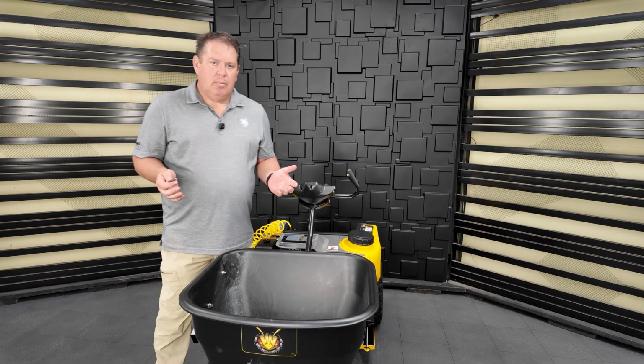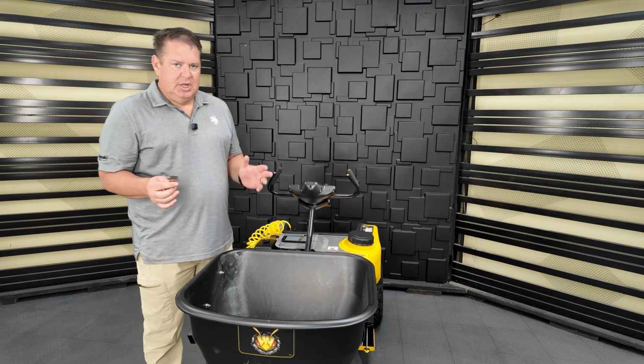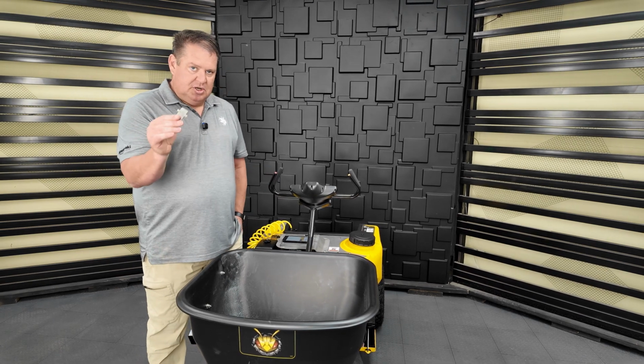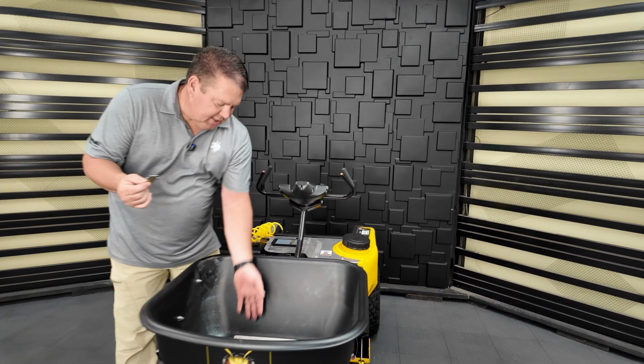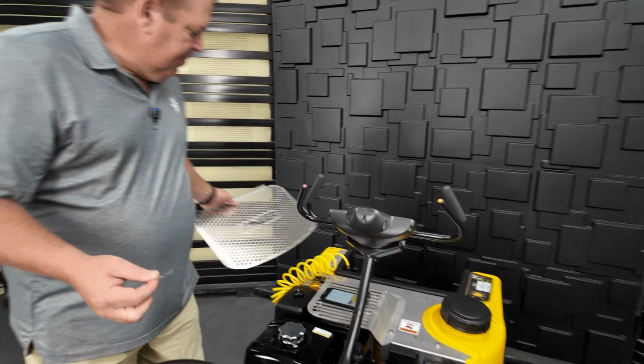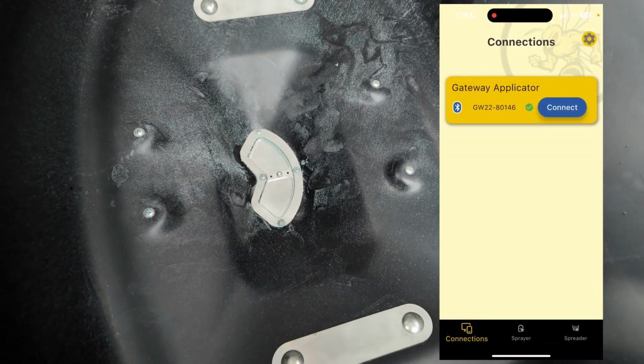The first thing you do in the calibration process, or even setting up any machine, is set the min and max position. Use the feeler gauge that came with your calibration kit. So I'll take the screen out, get my OneTouch app, log in, and connect to the machine.